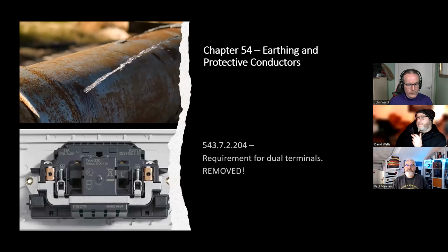John? Yep, Chapter 54, Earthing and Protective Conductors. 543.7.2.204. The requirement for having dual earth terminals on the back of your accessories has been removed. Indeed, you don't need it anymore. That's one of the requirements removed from this whole installation leakage. The enhanced coverage of RCBOs removes the need for this. Yep. So all that thing about having a ring of protective conductors with separate terminals and all that, gone away.